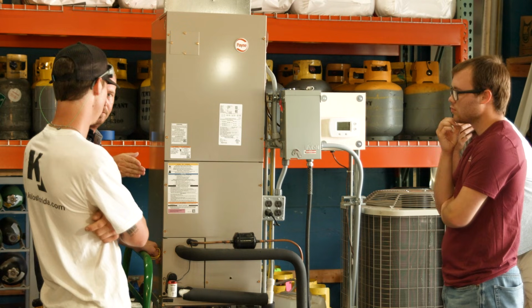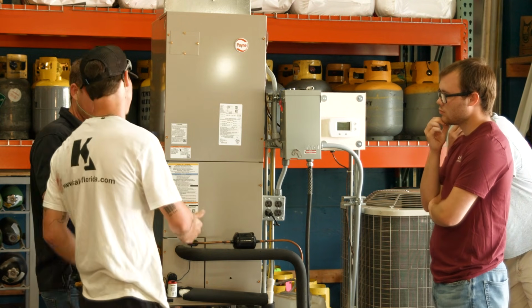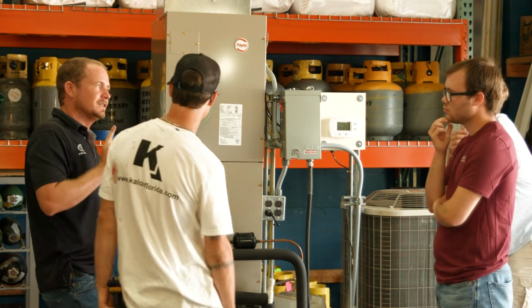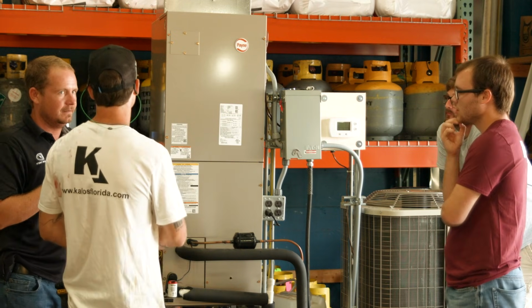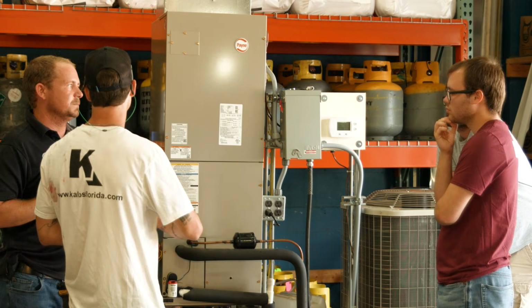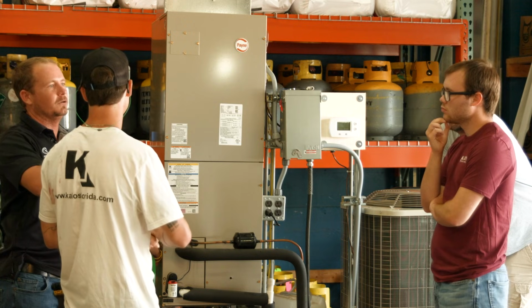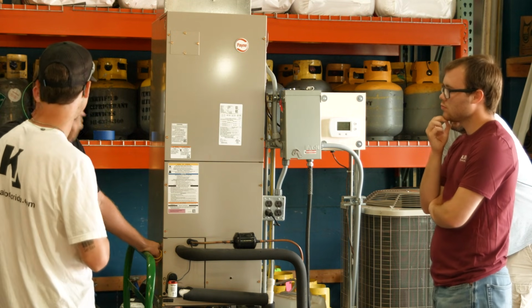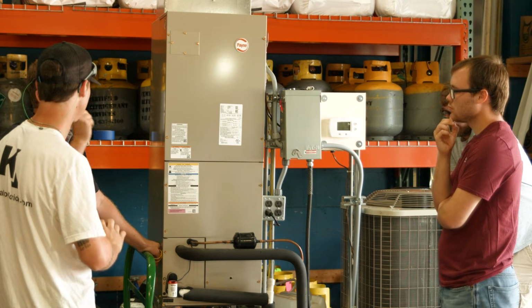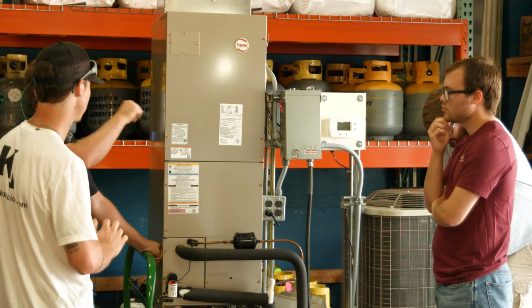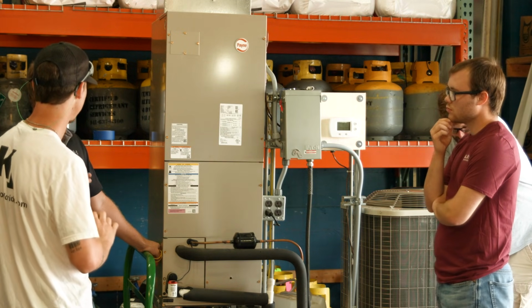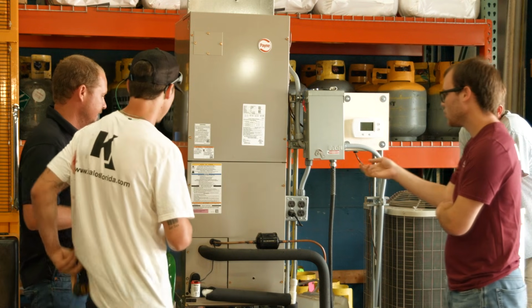It kicked on real quick and then it shut off. So what's most likely, because it did kick in, we popped the fuse. It's most likely that you popped a fuse, right? Because if it was, for example, a common that was completely disconnected, it wouldn't have come on and then gone back off again. So using your senses to diagnose is always first. Let's go ahead and get it open.